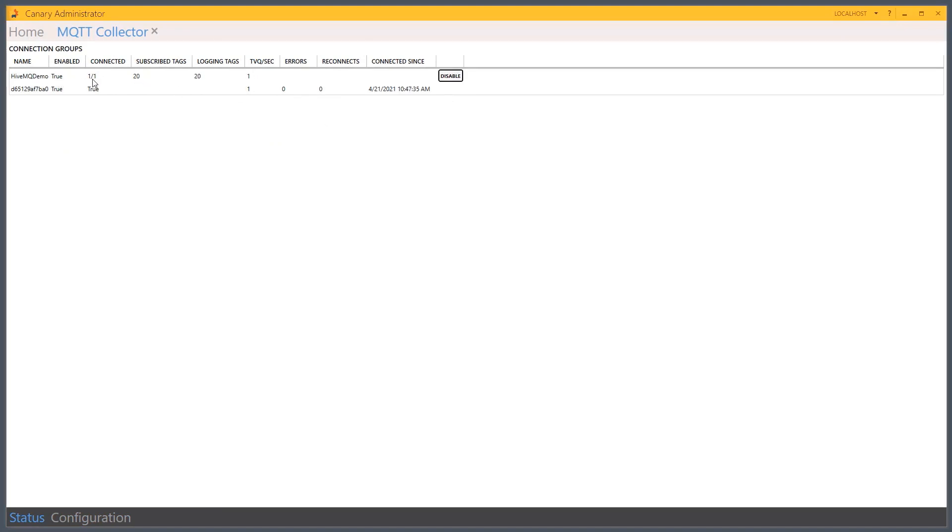And we'll see that I've connected. And my connection is good. We found 20 tags. We're logging 20 tags. And that data is currently coming in to the historian.